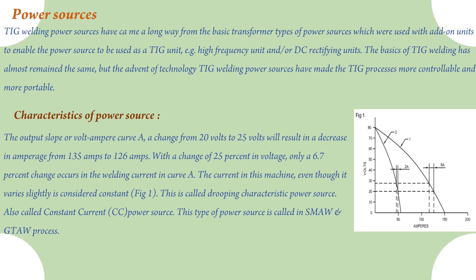Characteristics of power source. The output slope or volt-ampere curve: a change from 20 volts to 25 volts will result in a decrease in amperage from 135 amperes to 126 amperes. With a change of 25% in voltage, only a 6.7% change occurs in the welding current in curve A. The current in this machine, even though it varies slightly, is considered constant, as shown in figure 1. This is called a drooping characteristics power source, also called a constant current (CC) power source. This type of power source is used in shielded metal arc welding and gas tungsten arc welding processes.